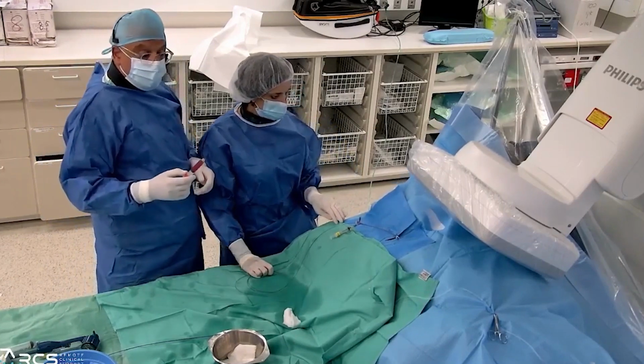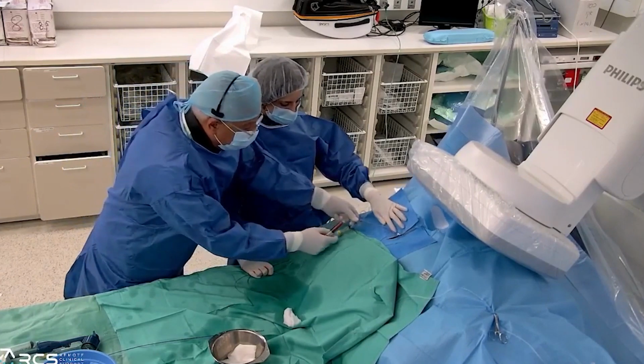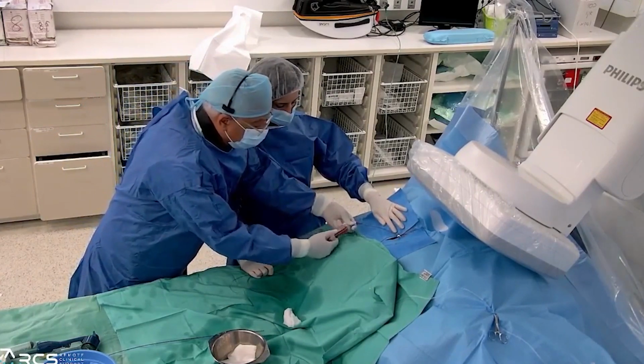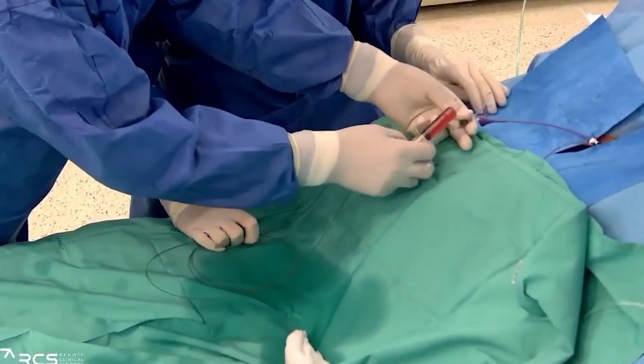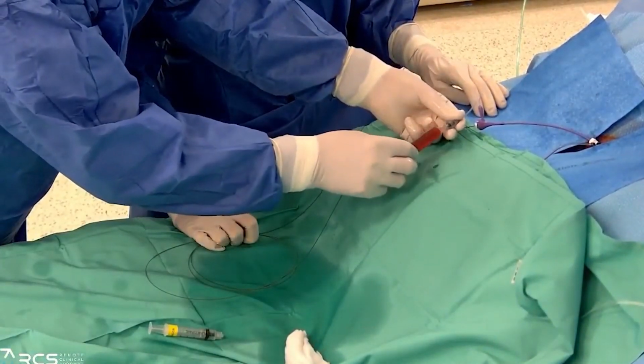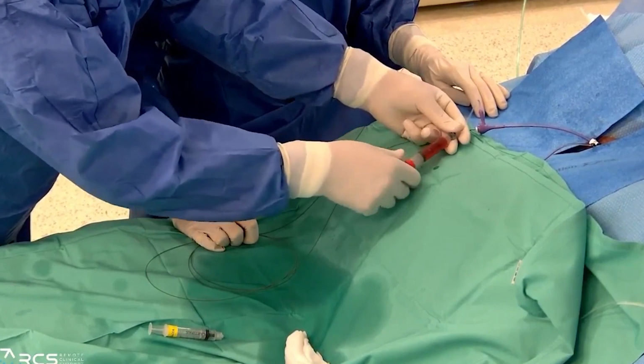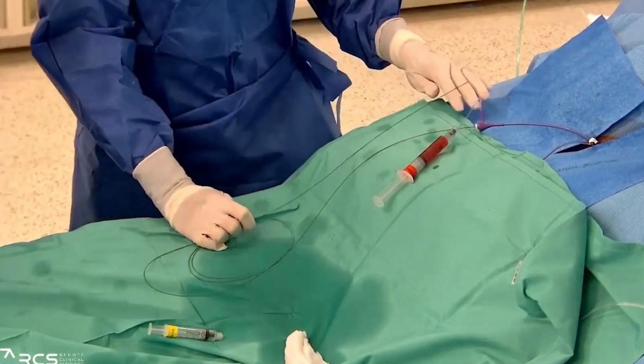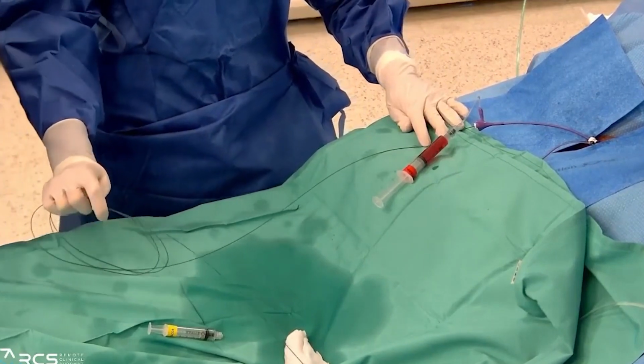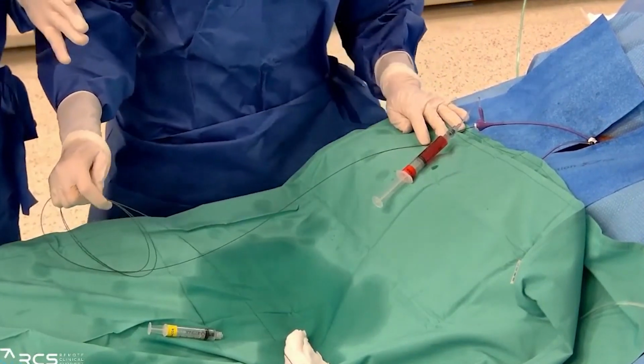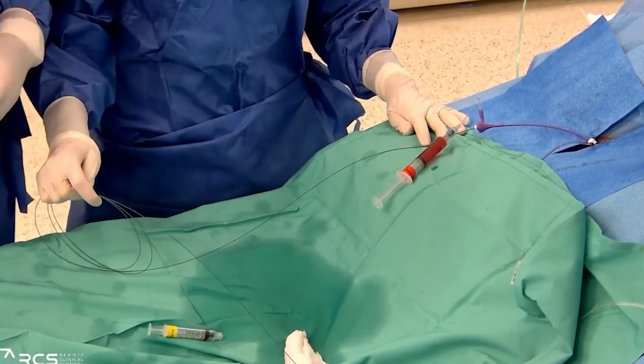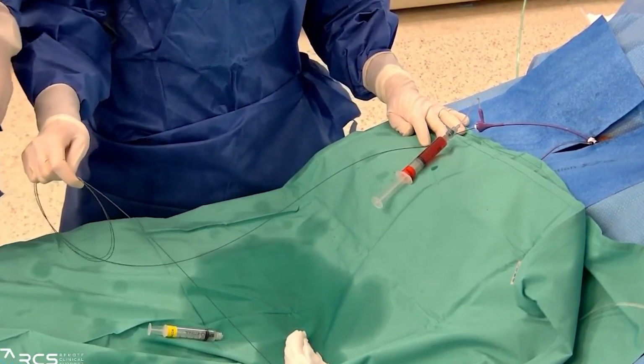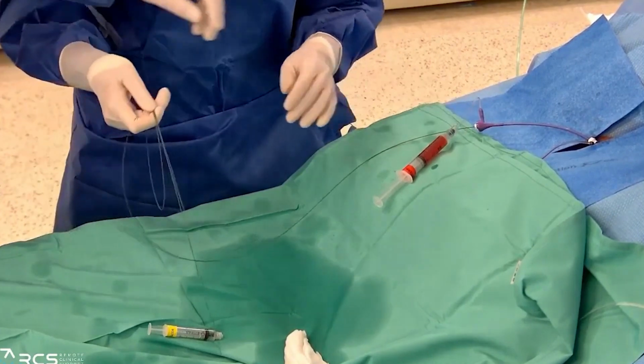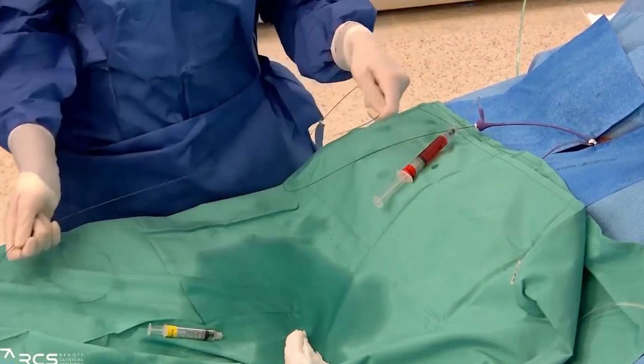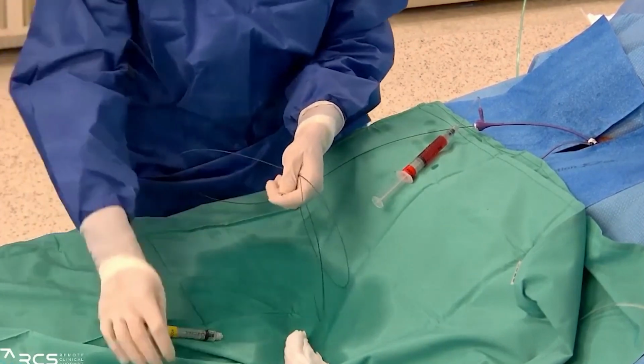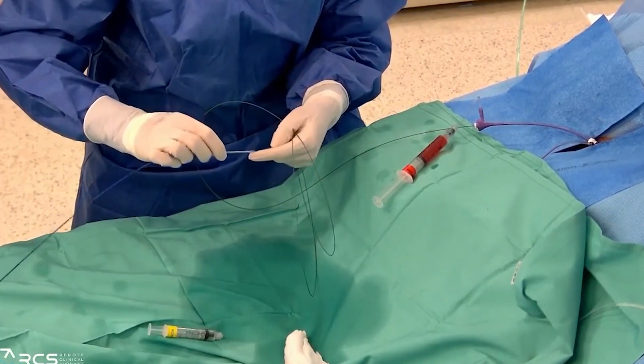So in order to verify that we are oversizing sufficiently, I will put here on the side port of the guiding a syringe with contrast. And when the reducer is fully inflated, we will inject some contrast through the guiding catheter to make sure that no contrast is going around the balloon and that we are sufficiently oversized. So now Marianne will take the reducer, put it over the wire, and get the reducer to the level of the right atrium and then stop.